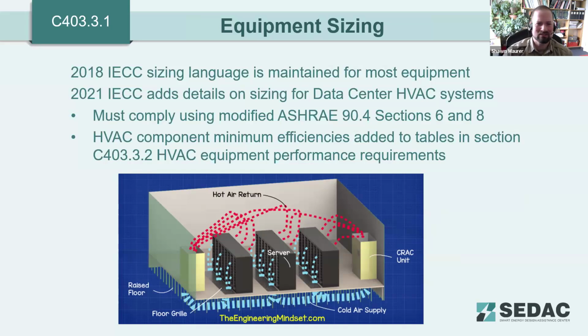So updates to the mechanical section. C403.3.1 has specific requirements for equipment sizing for data centers and HVAC systems now added, where this was not a separate section in the 2018 IECC. So equipment sizing must comply using the modified ASHRAE 90.4, sections 6 and 8. And the modifications are contained in the 2021 code. We won't get into them in detail, but know that there's a slightly different load calculation methodology for data centers than there is for other building types.